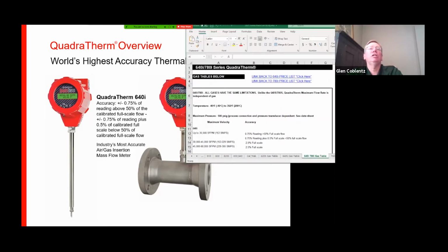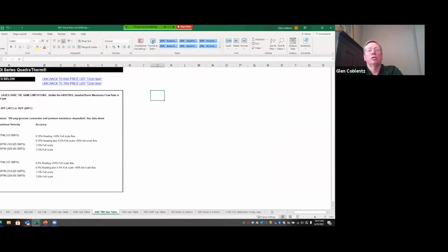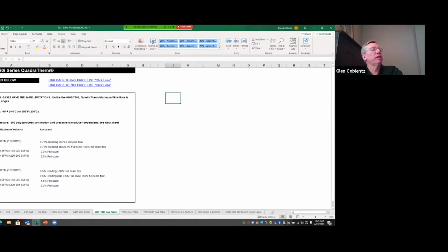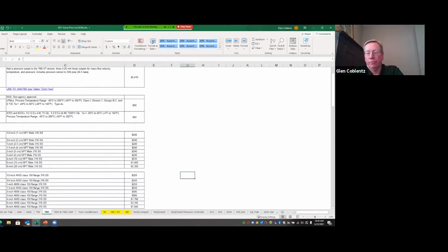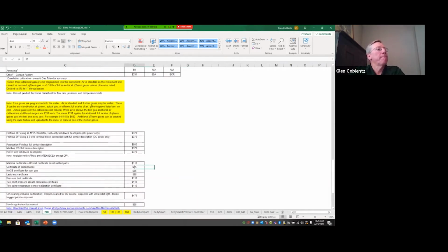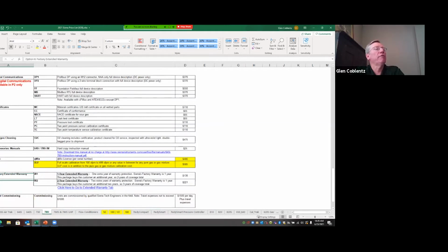And a good way to see this is if we look here at the full scale flow rates listed for the 640i up to 30,000, 30,000 to 45, and the same thing here. And you can see what the accuracies are here. So anything up to 30,000 standard feet per minute would be this accuracy statement. Now, as I mentioned before, the minimum full scale that you can go to is 0 to 100. But any flow rates that the calibrated full scale 0 to 100 up to 0 to 499 is considered a ULF calibration, and there is an adder for that ULF calibration. You would find that in the actual price list right here. If you go down to the bottom, you will see the ULF definition. Full scale calibrations 0 to 100 up to 0 to 499.